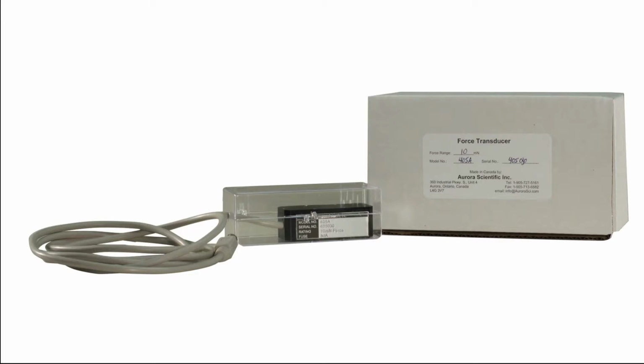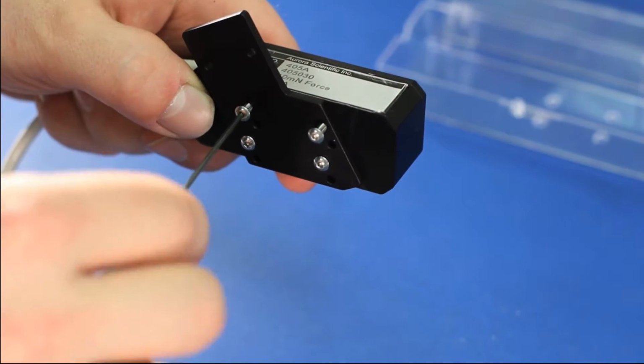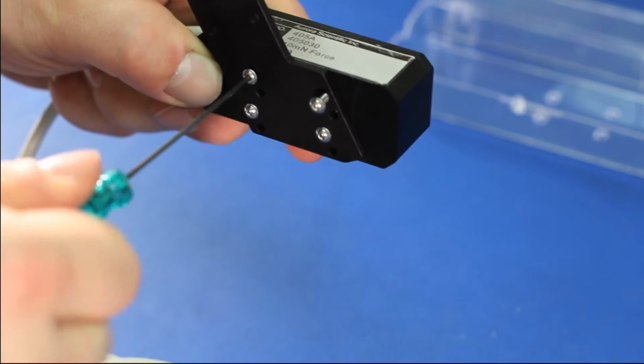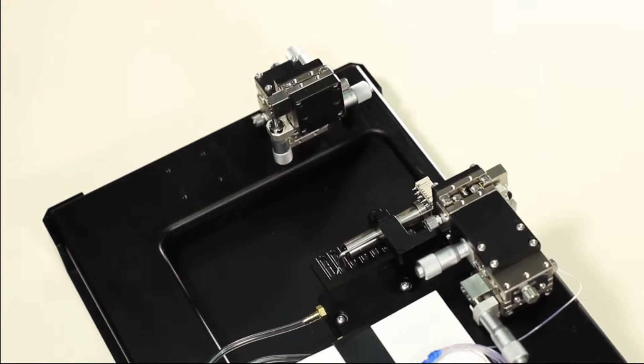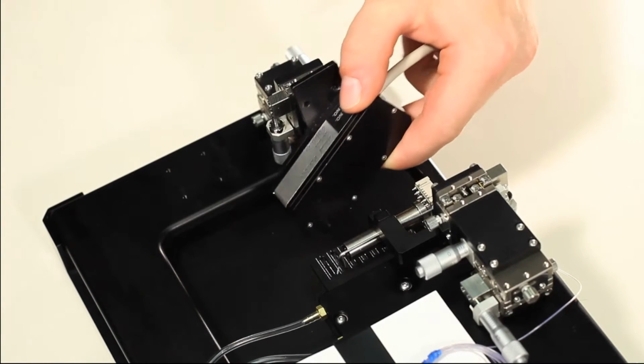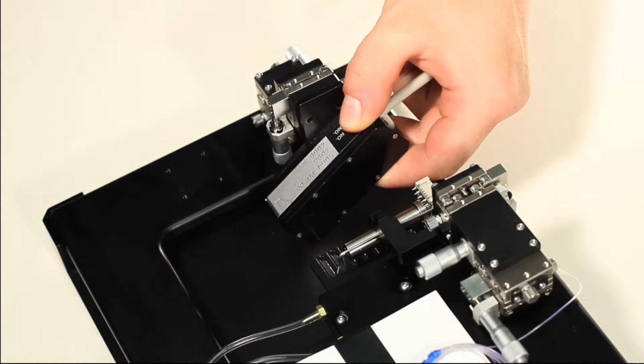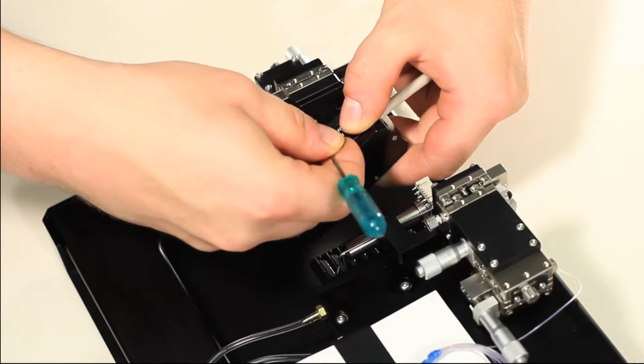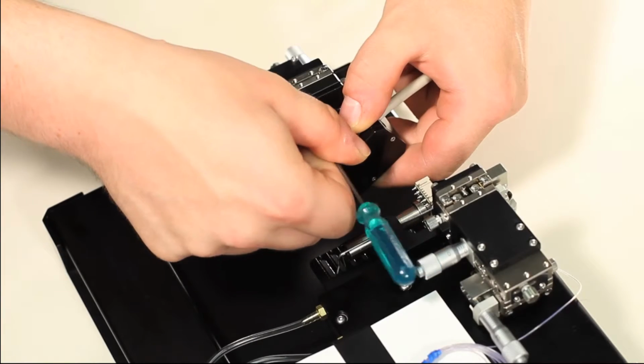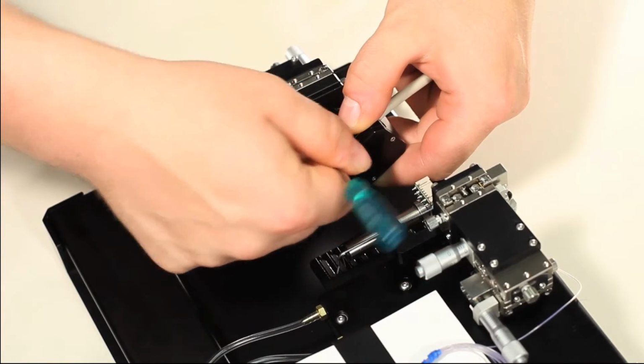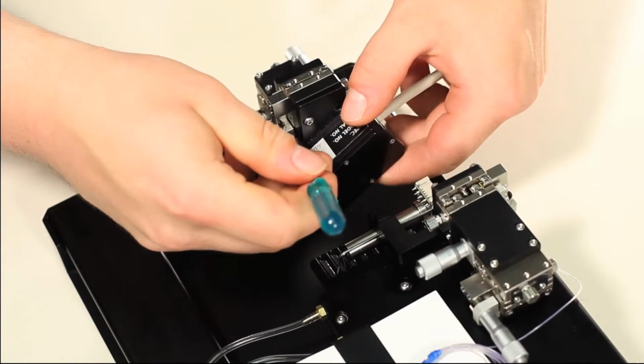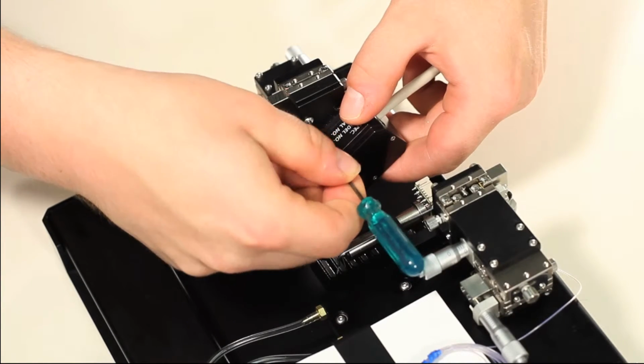The force transducer should be attached next. Remove the mounting plate from the apparatus and use the provided screws to mount the transducer head to the plate as shown. Then remount the plate to the 802D apparatus. Be careful to prevent the force transducer output tube from contacting the 802D apparatus, as this could damage the transducer.